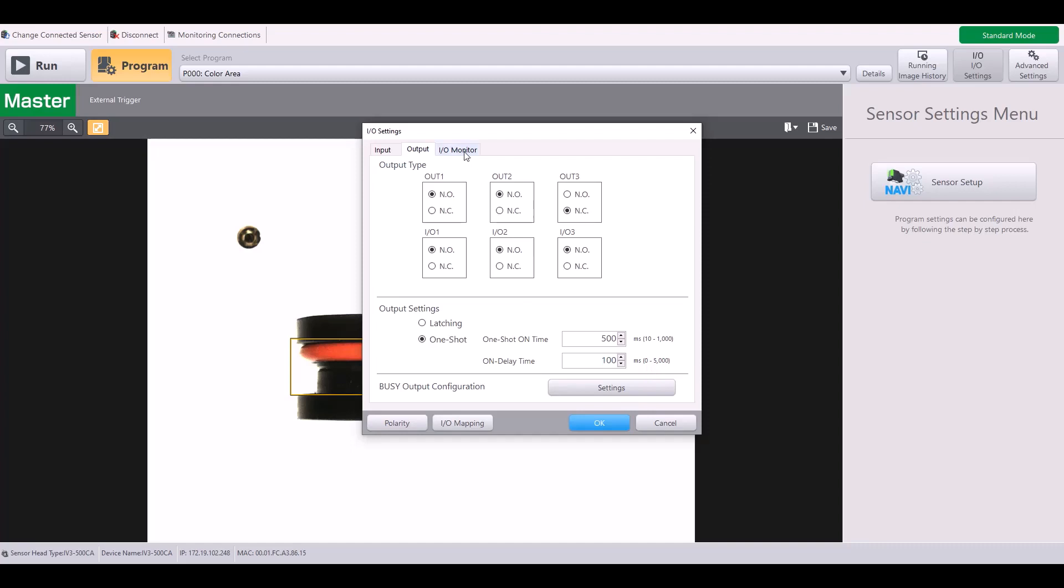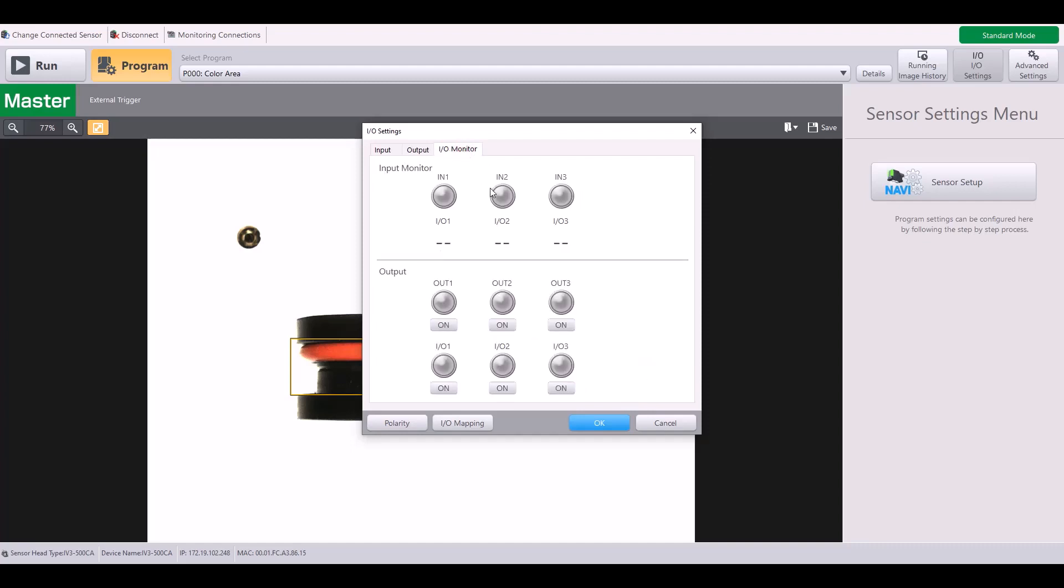Lastly, if we jump into IO Monitor, this can be really useful for troubleshooting purposes by manually turning on the output at different times to verify whether your third-party device, whether it's a PLC, a stack light, etc., is receiving that signal. You can just make sure it's on or off.